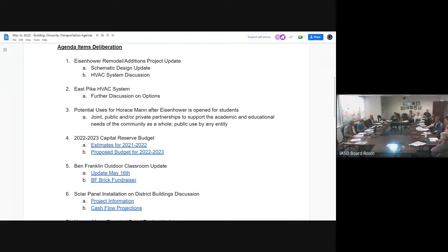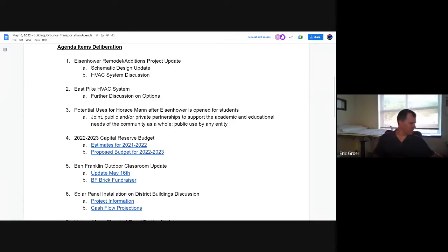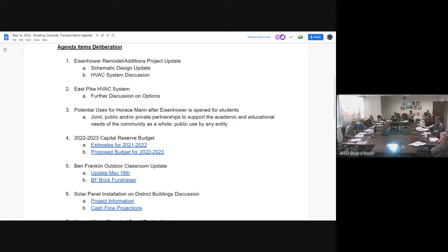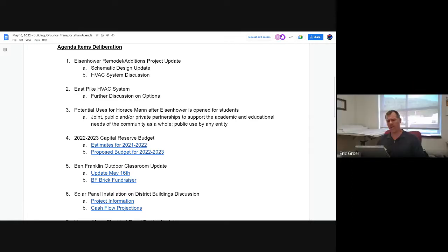Eric, according to your calculations of tonnage, you're indicating about 140 tons of air conditioning needed for the new building in the geothermal model - is that true? Your well field is 55 wells at 500 feet, at 2.5 tons per 500-foot well. Yeah, I came out to about 120 tons of cooling and about 150 tons of heating, so I sized the well field based on the greater of the two, which was the 150 tons of heating.